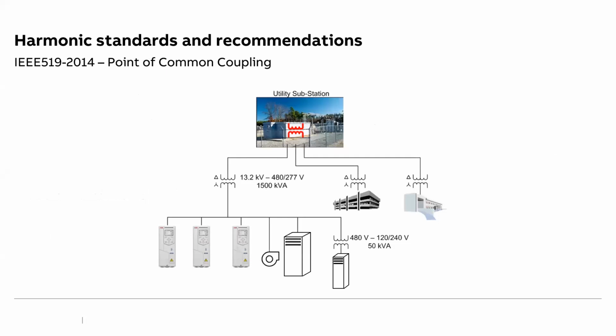As per IEEE 519, wherever there is a handshake between the power supply company and the user, at the premises of the end user, that point becomes the point of common coupling. Mostly it would be the secondary of the transformer. So that becomes the PCC. However, we can define multiple PCCs further down the network also.